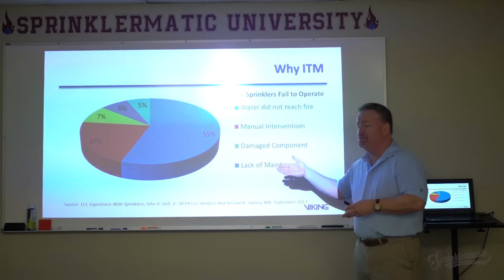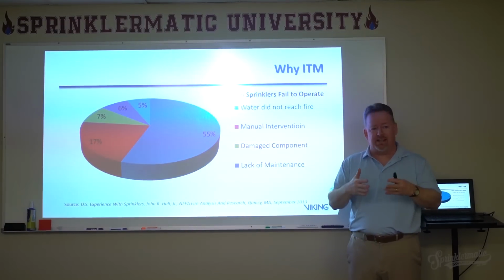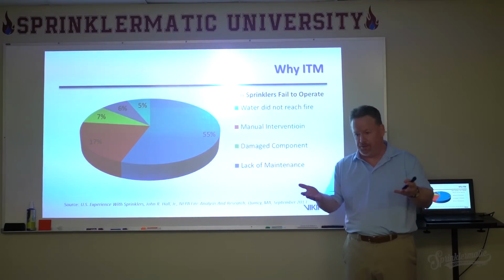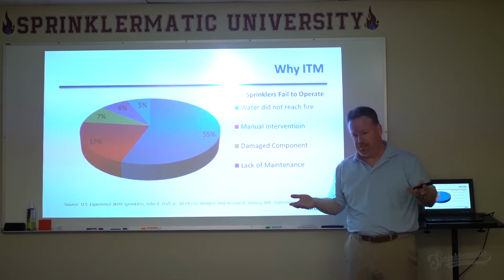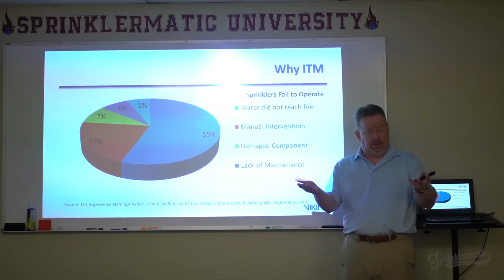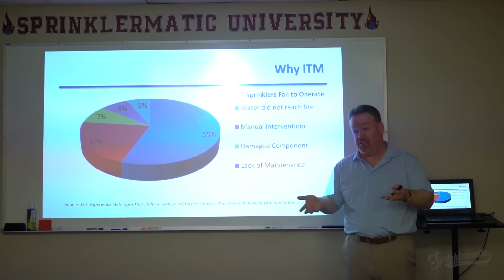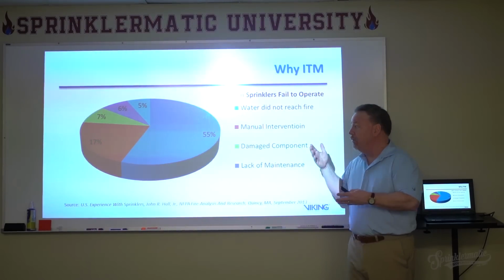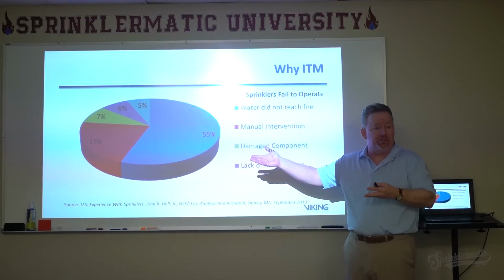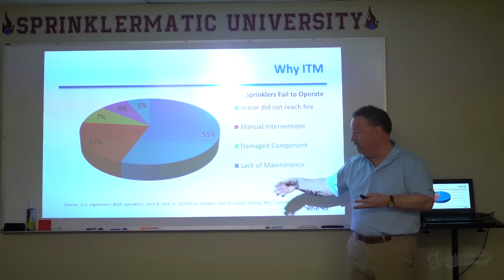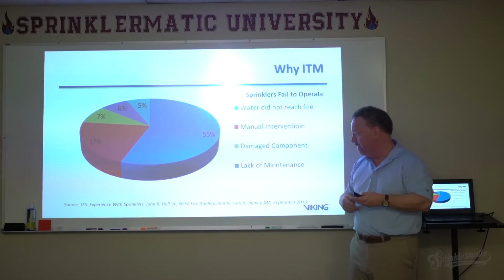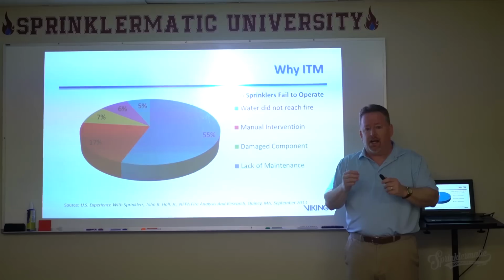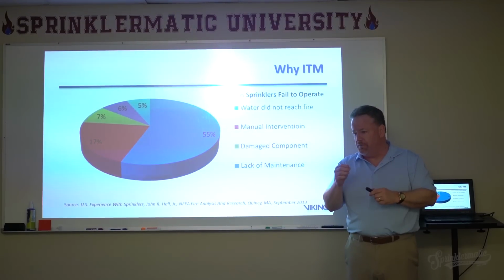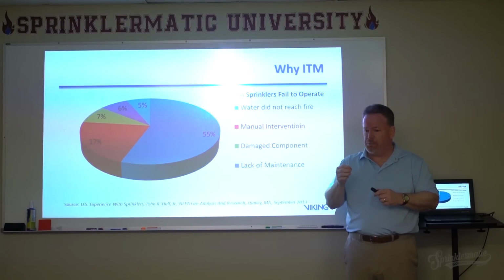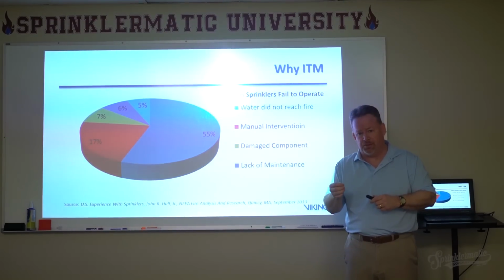Primarily we have inspection, testing, and maintenance even though we've got a 95% success rate — sprinkler systems are successful 95% of the time when asked to do something, over years and years of data collected by NFPA through the Fire Analysis and Research Division. That data shows that 95% of the time, sprinklers are successful in doing exactly what we've designed them to do.